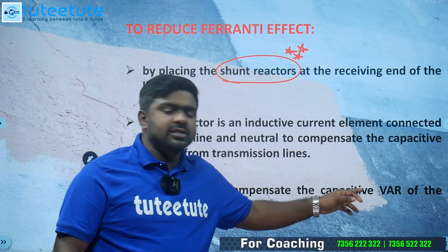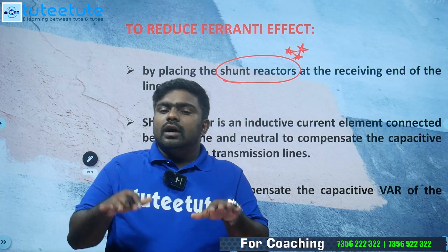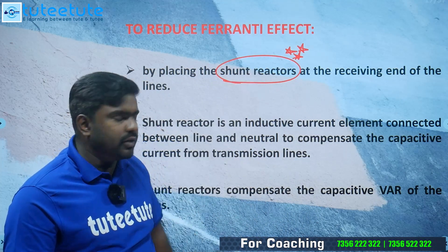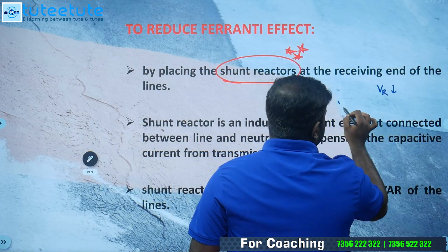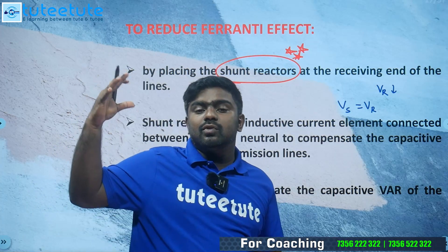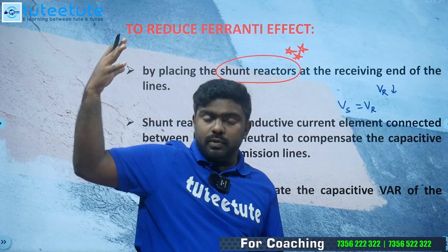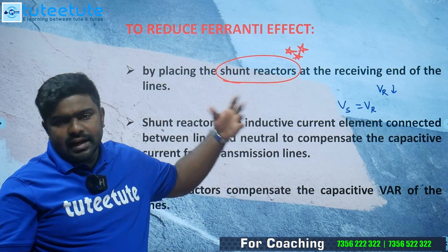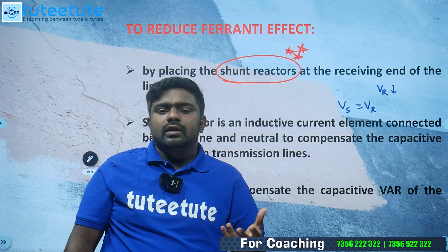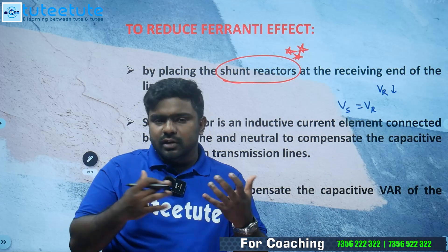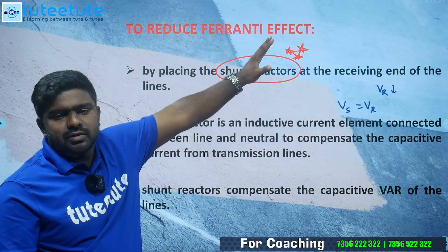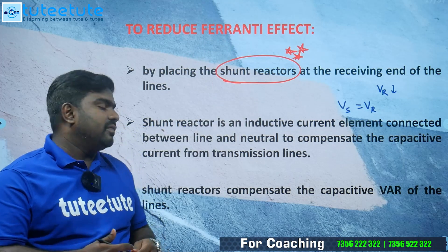The shunt reactor compensates the capacitive volt-ampere reactive of the line. The rise in potential at the receiving end due to the capacitor will be made flatter by the inductor, so VR will reduce and become equal to the sending end voltage. That means we achieve smooth power flow where VS is more than VR — the normal power flow condition. Under lightly loaded or open-circuited conditions on a long transmission line, due to the capacitive nature and distributed parameters, capacitive current causes the receiving end voltage to rise. By using a shunt reactor, this can be made flatter or even lesser.